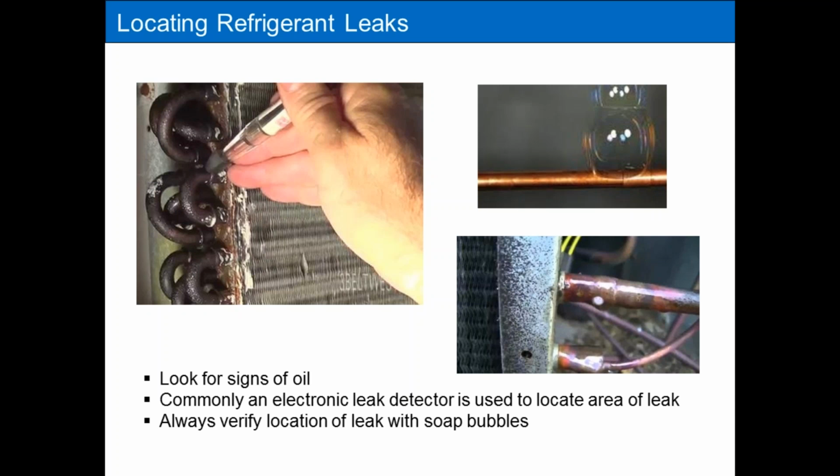Just as a heads up, a lot of times these units will leak in the evaporator coil due to the acidity of the products being in the case.